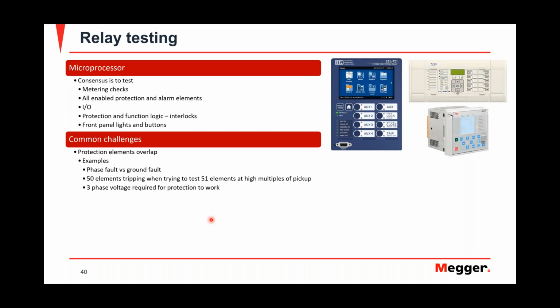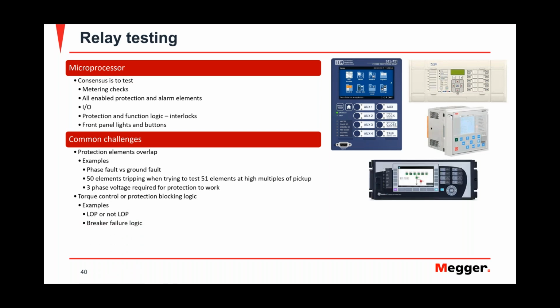Sometimes certain elements require 3-phase voltage to be applied for that element to work. Otherwise, the element doesn't work. So you have to go through the relay manual and understand how the relay wants you to perform that test. Some examples are the loss of potential or not loss of potential. That's very big on Schweitzer relays. A lot of functions either have the breaker failure logic or the loss of potential logic. So make sure you have an understanding of how that logic works, the loss of potential and the breaker failure.